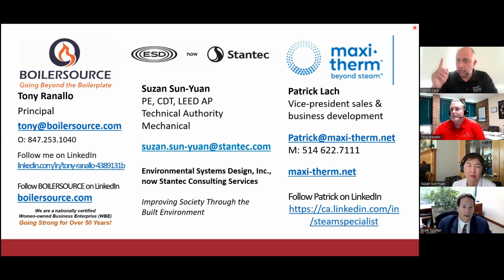One thing I'd like to add, Scott, is that there are two ways to go low temp. Let's say you're on a big campus. Number one, you run natural gas pipe everywhere on the campus, and in every mechanical room you have a condensing boiler to do low temp. Or number two, you have a distribution system of hot water all across the campus. Let's say it's 50 years old. In scenario one, you're going to start to have natural gas leaks, and that will be emergency care. In scenario two, you're going to start to have hot water leaks, and that will be emergency care as well. It's much more of a headache than repairing a steam leak, much more of a headache.